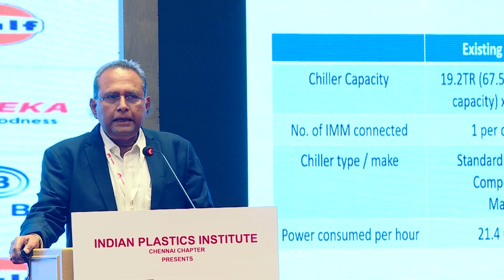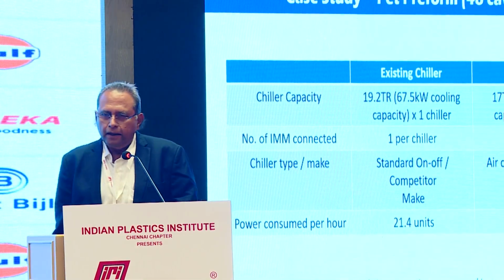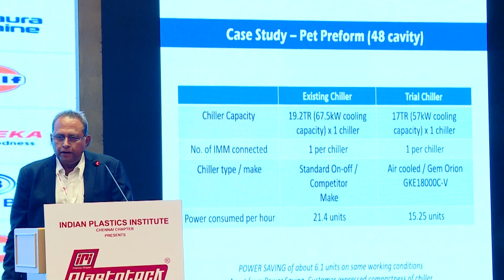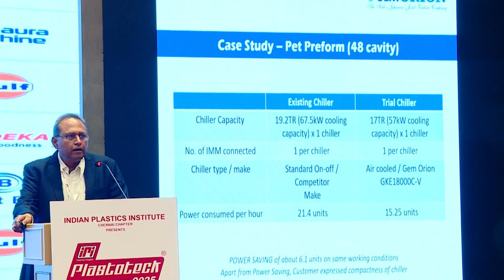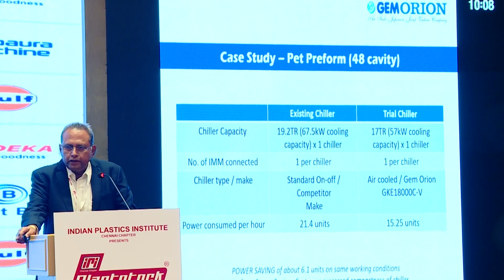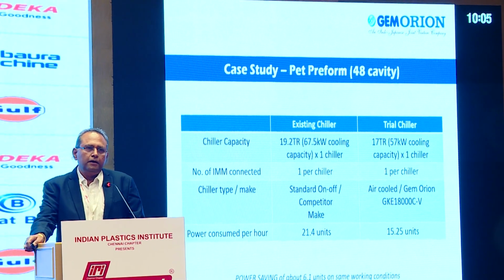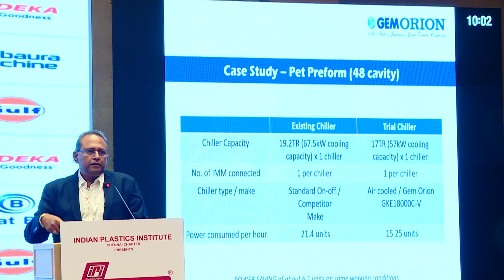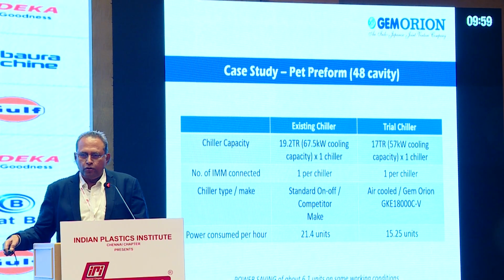So maybe you can have partial standby, the running costs can be drastically reduced, and water can become zero in that case. So this is also a typical chiller application for heat flow through hot well, cold well, and through intermediate plate heat exchangers where the water quality is bad. Typically, the case study we have seen is for a 48 cavity mold where an existing unit was replaced by our standard inverter chiller, and we were able to save almost 6 units per hour. So obviously the payback on the equipment will be very quick, maybe less than 2 years.